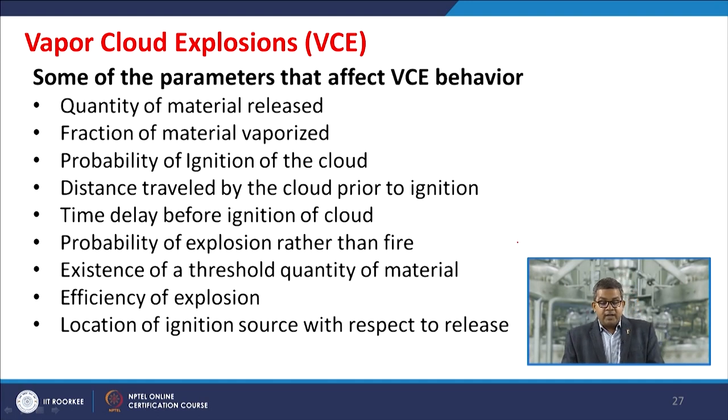Then, the distance traveled by the cloud prior to ignition. The reason is how much time is given to the cloud for dilution or dispersion, because if it escapes from the particular point where I am working, the concentration of hexane would be on the higher side, so probably it may be beyond the UFL. So, when it is released to the atmosphere, at what particular point of time or distance does it match the range of LFL and UFL?